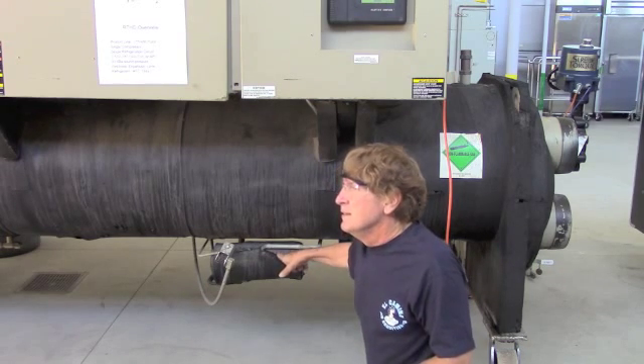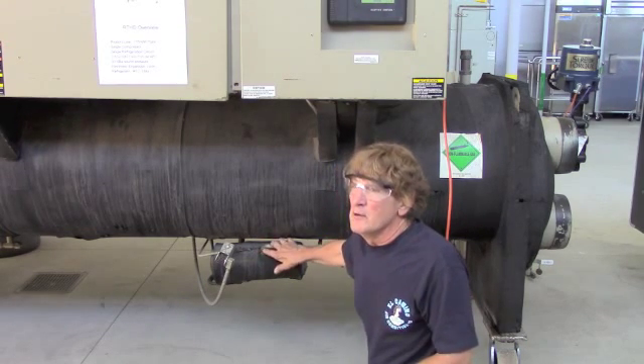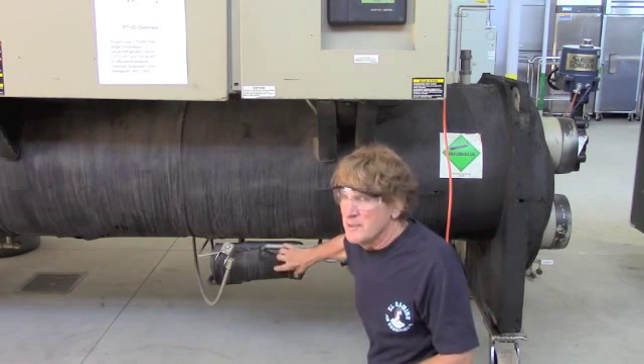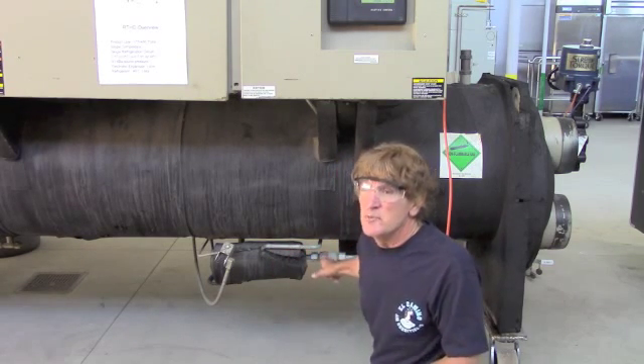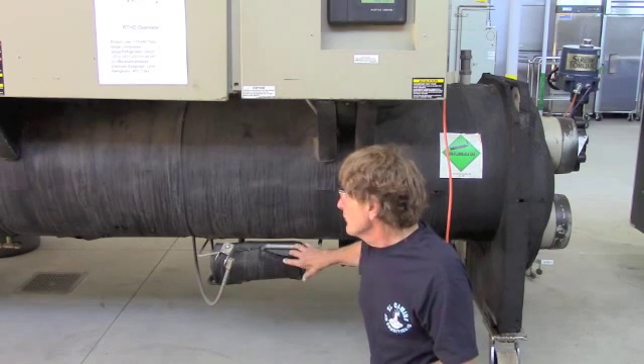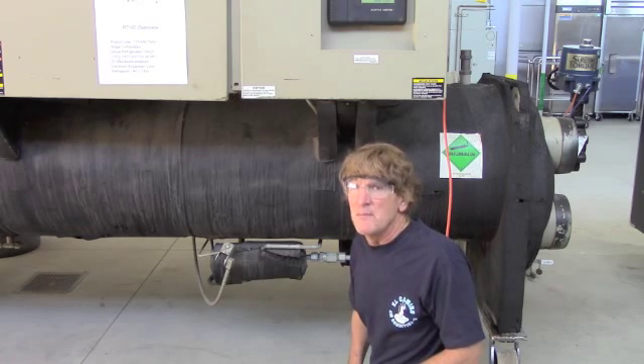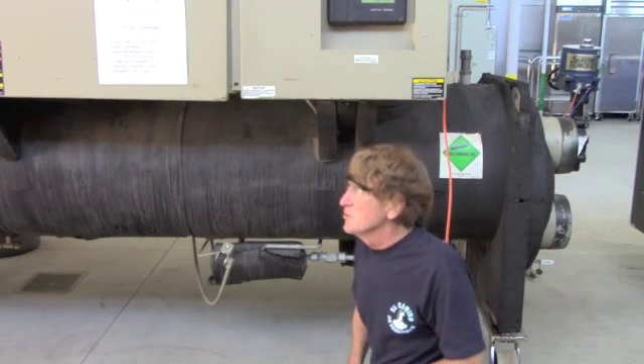And then, once it's filled, we'll energize another solenoid, which will pressurize the chamber itself. We have a check valve in here, to prevent oil and refrigerant from going back the other way. Pressurize this, and push it back up into the compressor. And that's my oil recovery for this particular chiller.